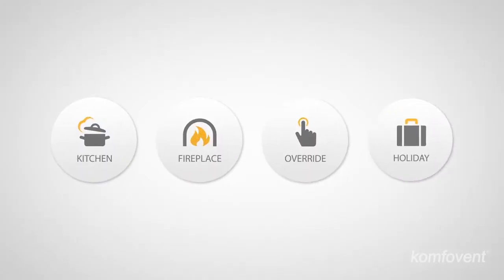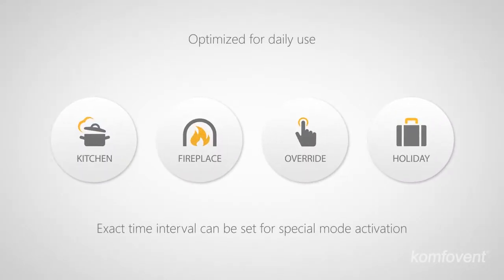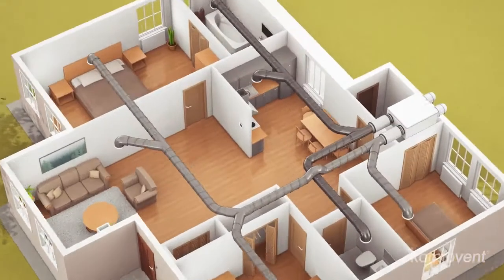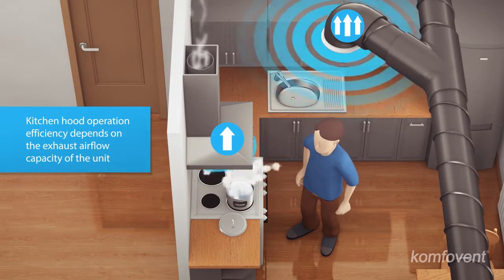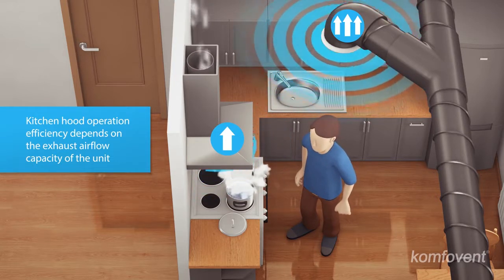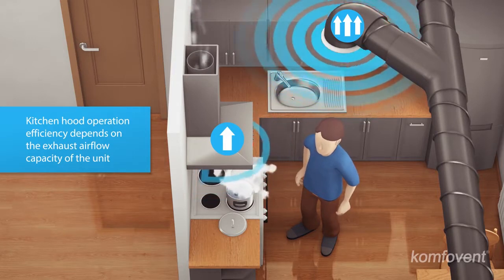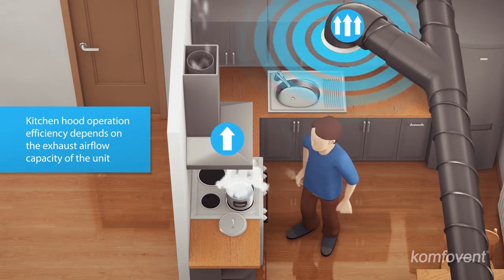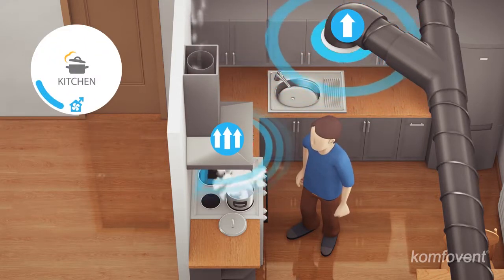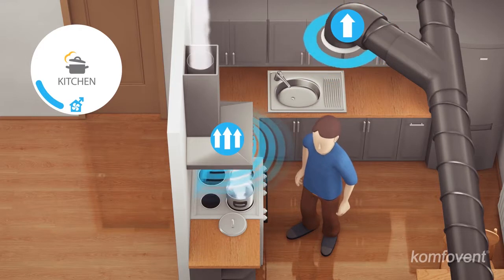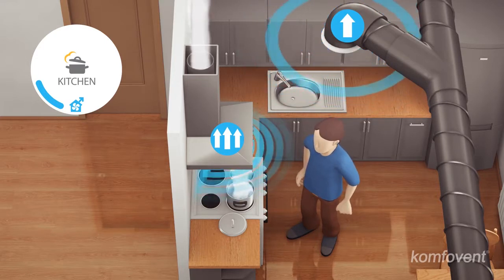Special ventilation modes allow you to save energy and ensure comfort in various daily situations. When you turn on the kitchen hood, it removes a large amount of air. Therefore, the pressure difference created between indoors and outdoors reduces the hood's performance and results in worse removal of odors and combustion products. Smart control allows you to select a special mode that reduces the air volume exhausted by the air handling unit, so upon adjustment of air flow, the hood can operate effectively.